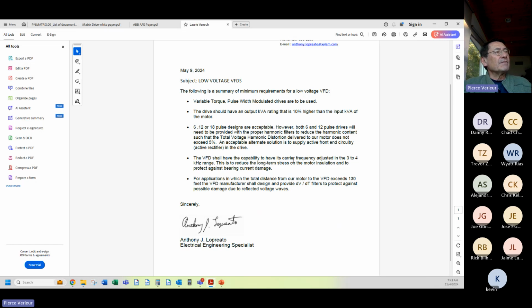The VFD shall have the capability to have its carrier frequency adjusted in the 3 to 4 kilohertz range. That's the switching frequency of the pulse width modulated waveform, and for a lot of reasons, that's a good idea. It reduces the amount of switching stress on the transistors in the VFD and allows the VFD to last longer. However, at 3 to 4 kilohertz, 3 to 4,000 times a second, that's right in the audible range of the human ear, and it will drive you freaking nuts if you're standing next to the motor. So you have to account for that too.